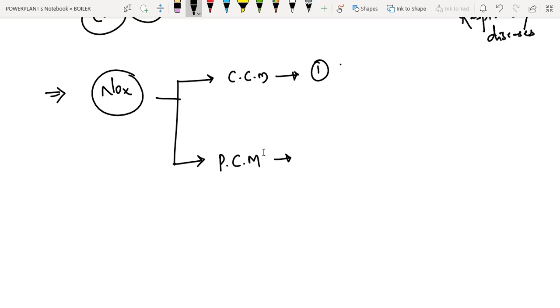In the combustion control method, we generally use different methods. The first one is reducing the temperature at the furnace, the second one is reducing excess air, and the third one is flue gas recirculation. That is, part of the flue gas after the economizer is sent back into the furnace, thereby reducing the temperature and also the oxygen requirement for the combustion.